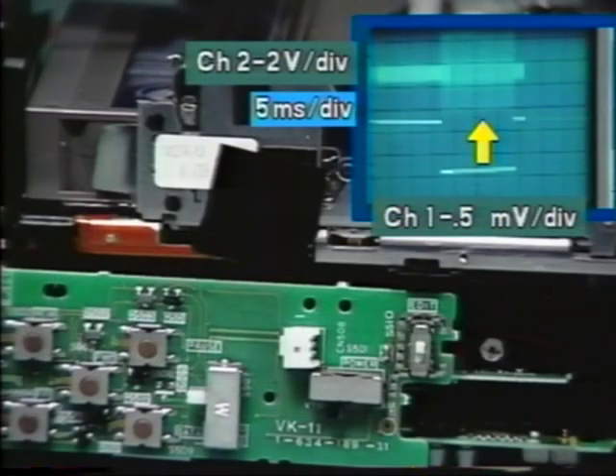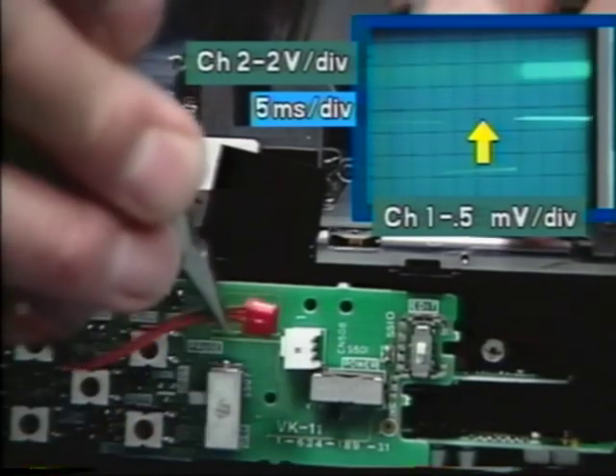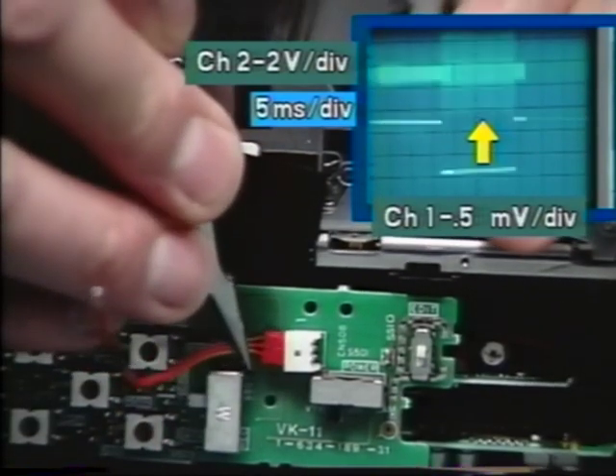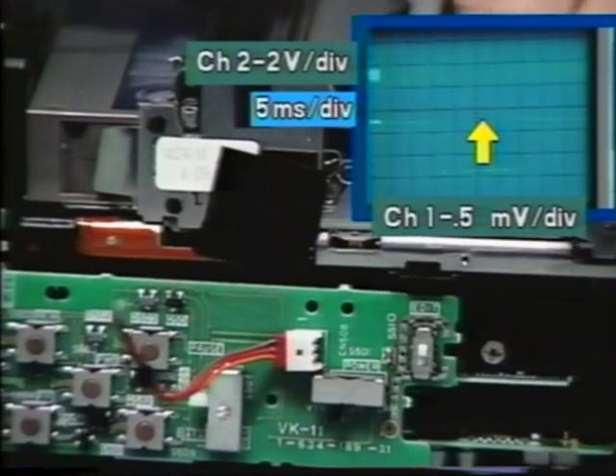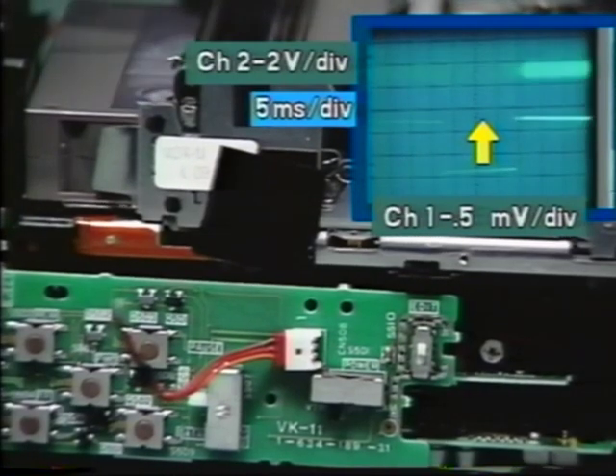In order to adjust tape path, you must first electrically force the automatic track finding servo to mistrack the tape slightly. This will aid in the proper alignment of the tape. To do this on this model, insert a 3-pin male connector with extended leads shorted together into CN508. When connected, notice that the RF video waveform is reduced in amplitude.